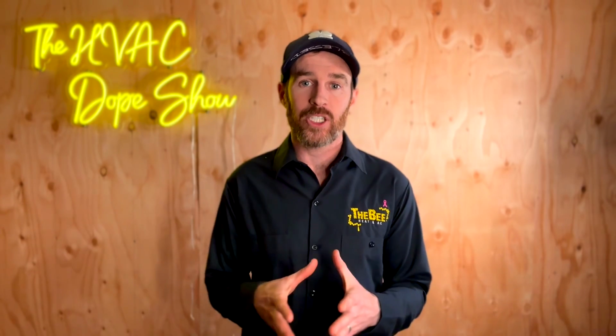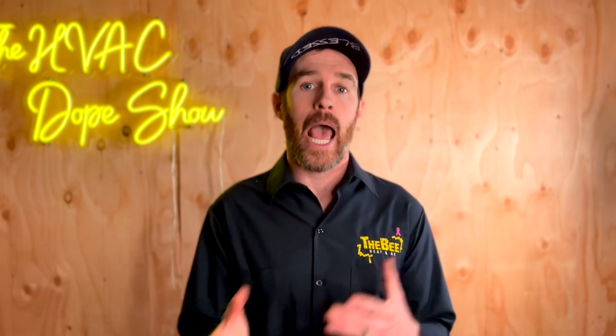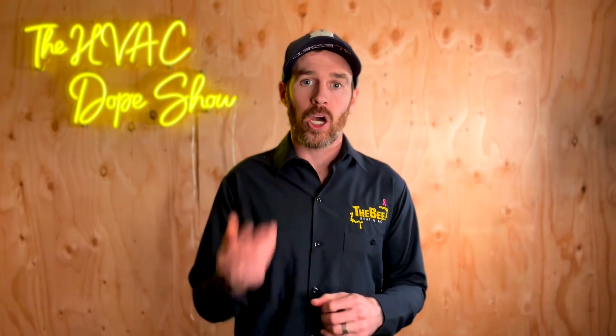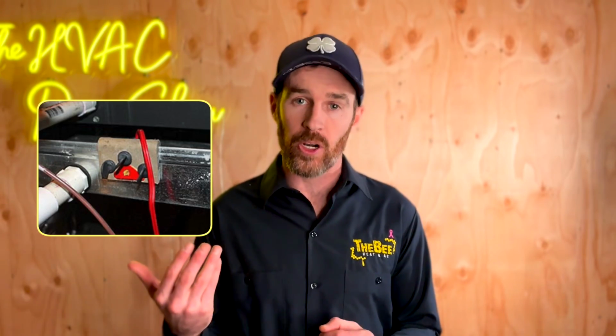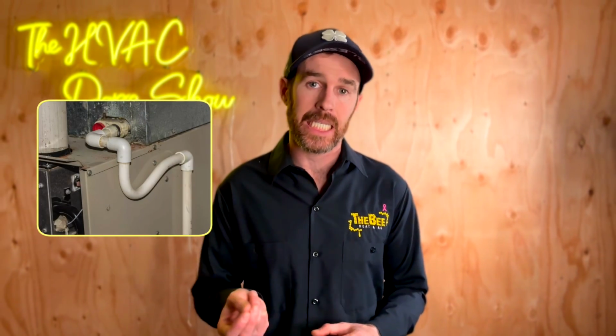Now, this condensation will freeze on very cold nights because it's just water, and that's going to happen where it exits the building if it is not insulated against cold. And if the condensate pump is backed up, it will then trip a float switch inside of itself that then turns off the furnace. And this is a really simple fix, and it can be avoided just by making sure that the condensate line itself is insulated against the cold.